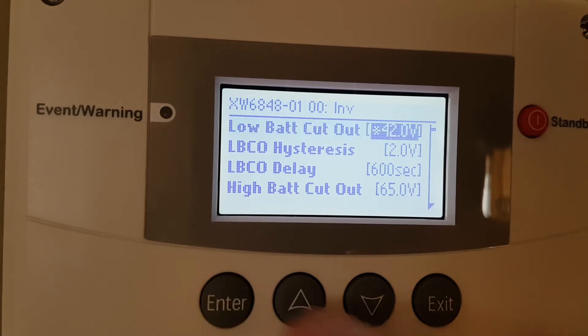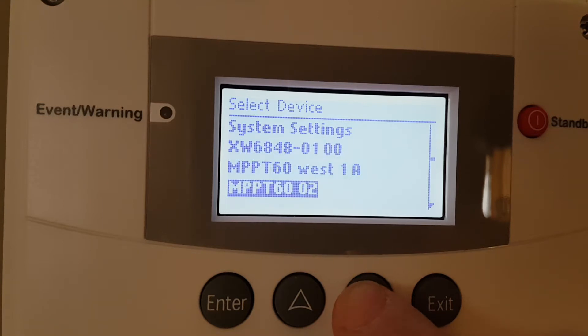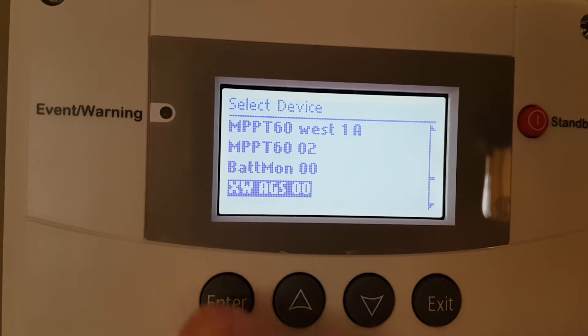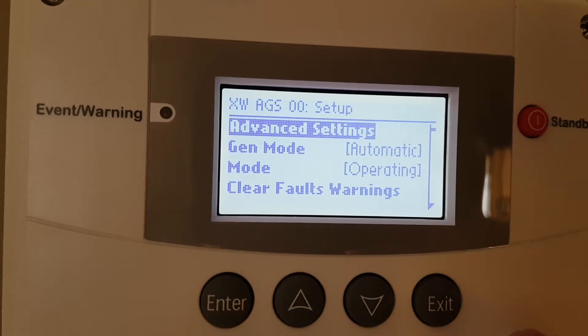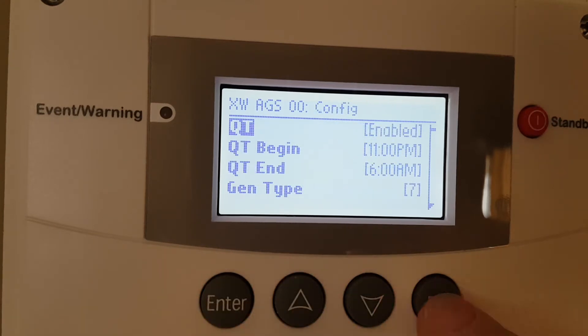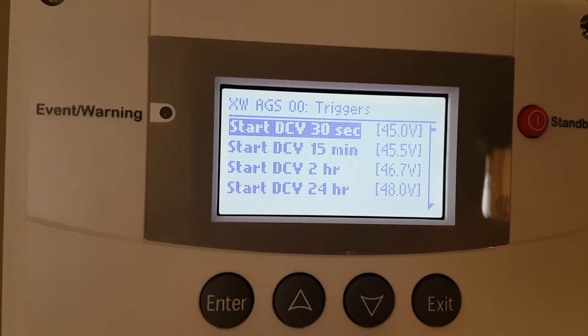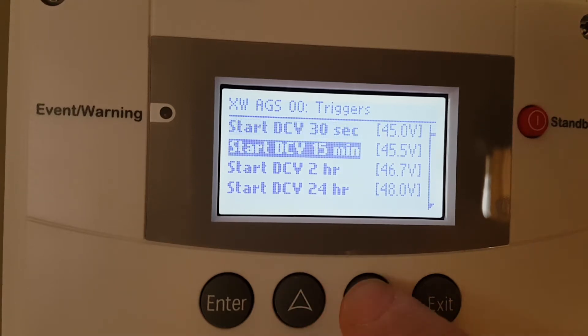So we had a look at that. Going to enter, go to exit, exit. Now we'll go down into generator. On a Schneider it's called an AGS — automatic generator start. My generator is on automatic and the mode is operating. We're going to have a look at advanced settings. Quiet times enabled, generator type — you type in your glow plugs, the relay functions, and how many seconds the cranking goes. Configuration trigger means what conditions will cause my generator to start. In your 30-second time you can see it's set for 45 volts, and then your 15-minute, two-hour, and 24-hour triggers.